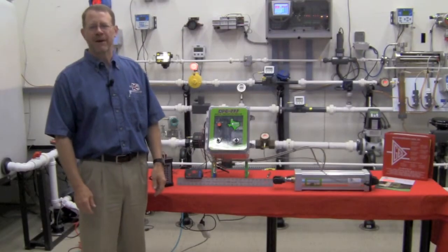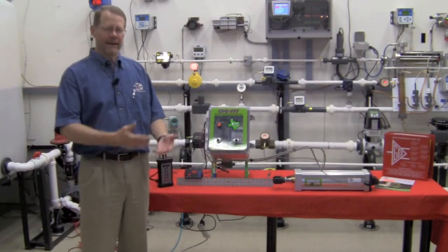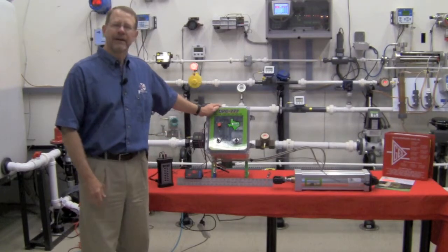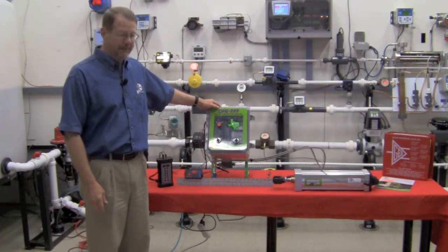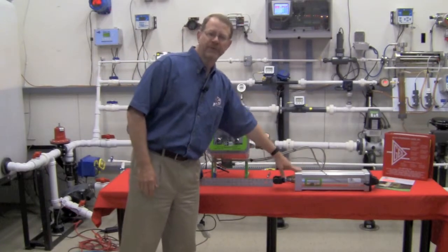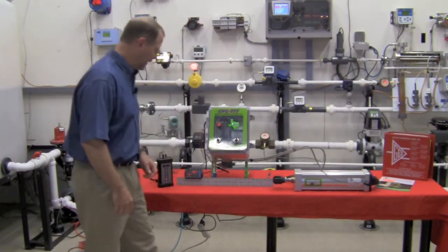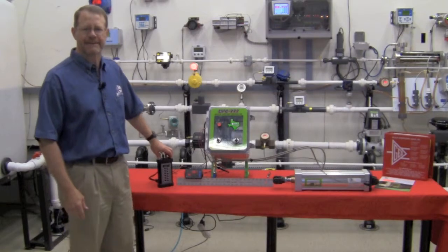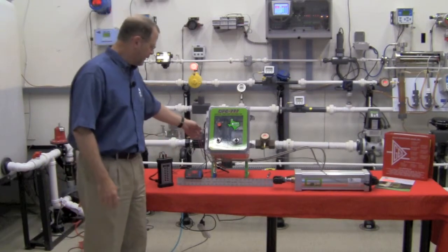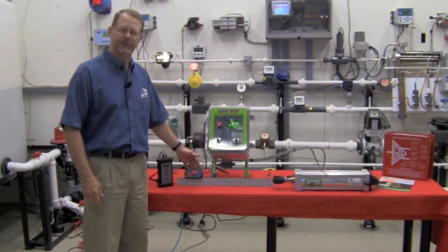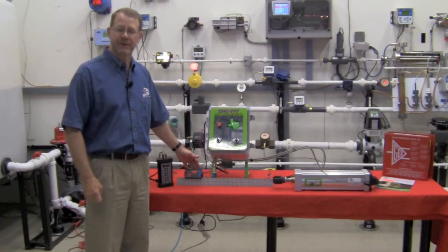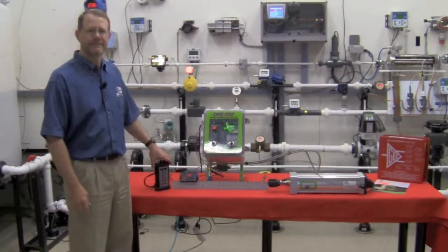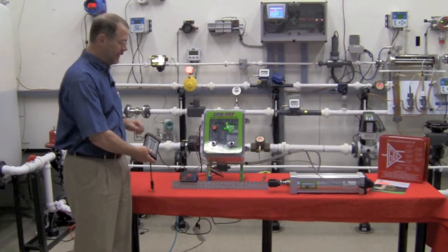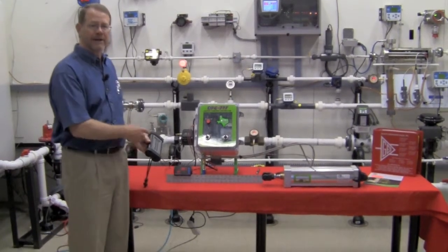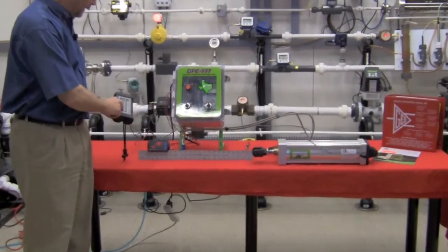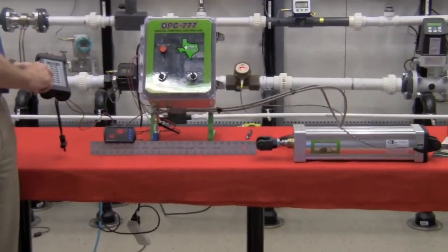Now allow me to demonstrate the operation of the JR linear drive and the DPC 777 and demonstrate its accuracy and repeatability. What we have here is a 12-inch stroke cylinder and a 4 to 20 milliamp source acting as our DCS. We also have a return or a feedback signal coming to a precision digital panel meter which has been scaled for 0 to 12 inches. Now please note the accuracy and the repeatability of the JR as I change our 4 to 20 milliamp inputs. At 4 milliamp we're at 0 inches.